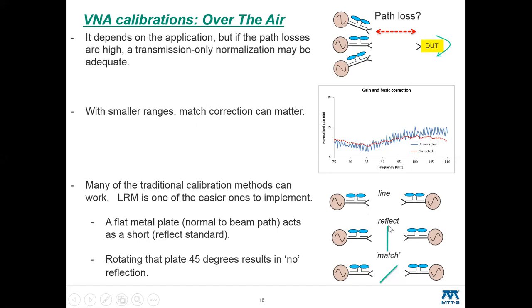So you can be a little sloppy with this standard and not take a big uncertainty hit. And for the match, while you could use an absorber, if you're in a chamber with reasonably absorptive walls, just tilting this plate at a 45-degree angle means you're getting essentially no reflection back into the antenna. That works reasonably well as a match standard.